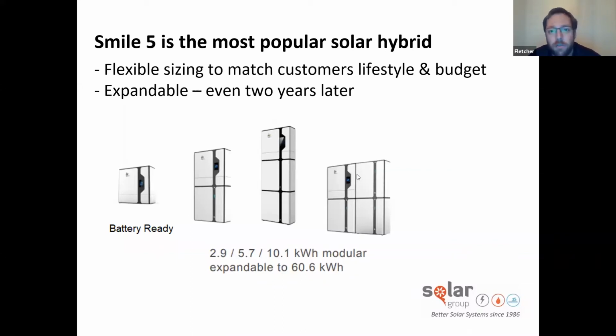The only thing to remember is you cannot mix and match battery types, since these batteries are all in parallel and therefore need to be identical sizes. So if you start with a 2.9, you continue with 2.9. If you start with 5.7, you continue with the same size. The largest system you can have is 6 of the 10.1 kilowatt hour batteries, giving you a max system storage of 60.6 kilowatt hours. This is why scalability is important, because you can start small and gradually build up.